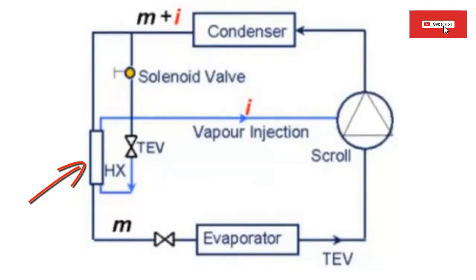7. The evaporated refrigerant I, through the heat exchanger HX, is injected into the compressors, providing additional cooling at higher compression ratios.